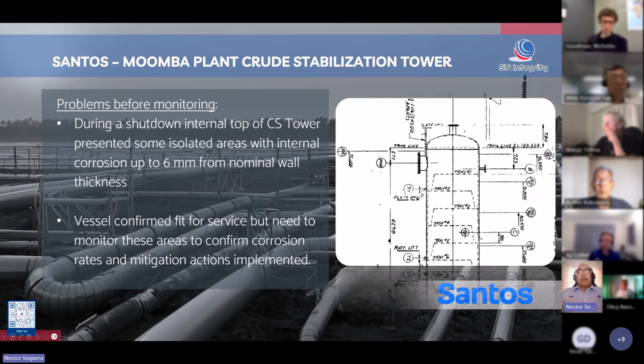What was the situation here? The plant was shut down, so they jumped into the tower to do internal inspection, to clean out the tower and assess the condition of it. And they found that at the top of the tower, they had corrosion areas with up to 6 millimeters loss from nominal wall thickness. They did a fitness for service calculation and found it to be still fit for service. Then they did a mitigation by blasting that area and putting a new coating in. And then they contacted us to see how we can help them to monitor that going forward.